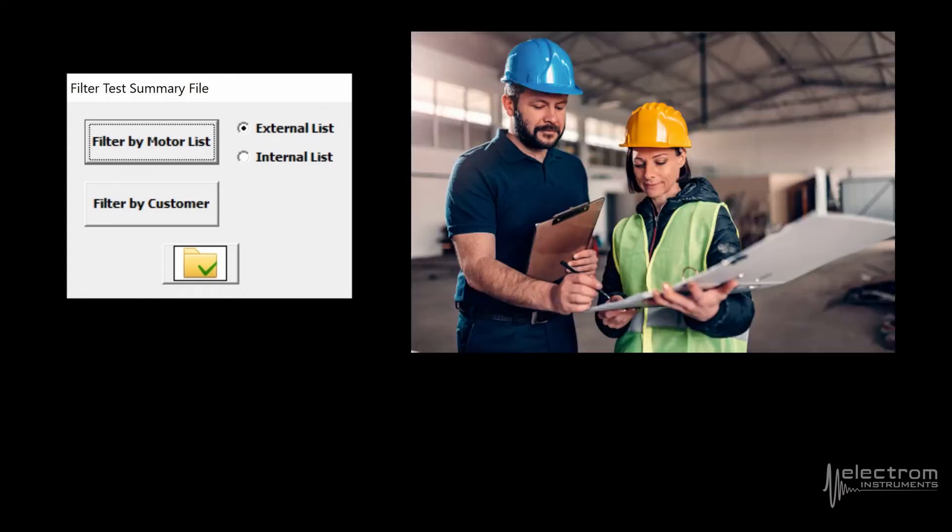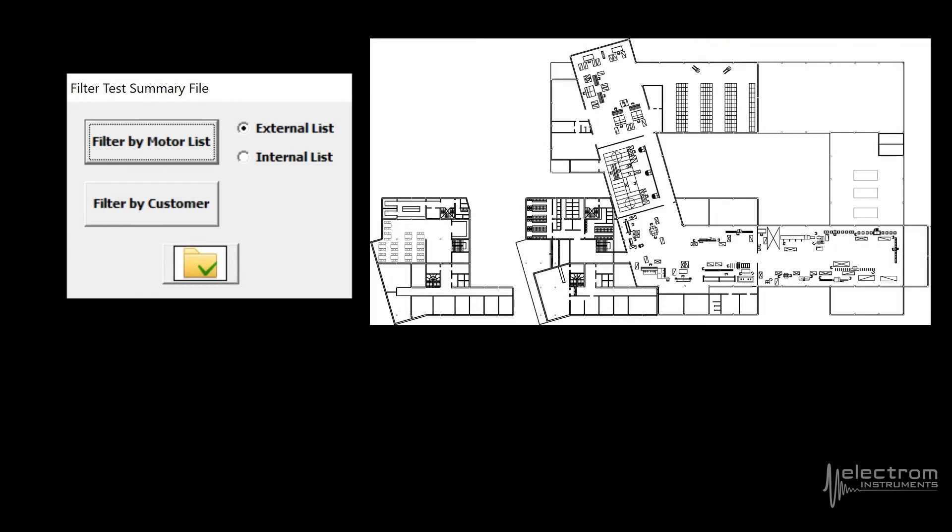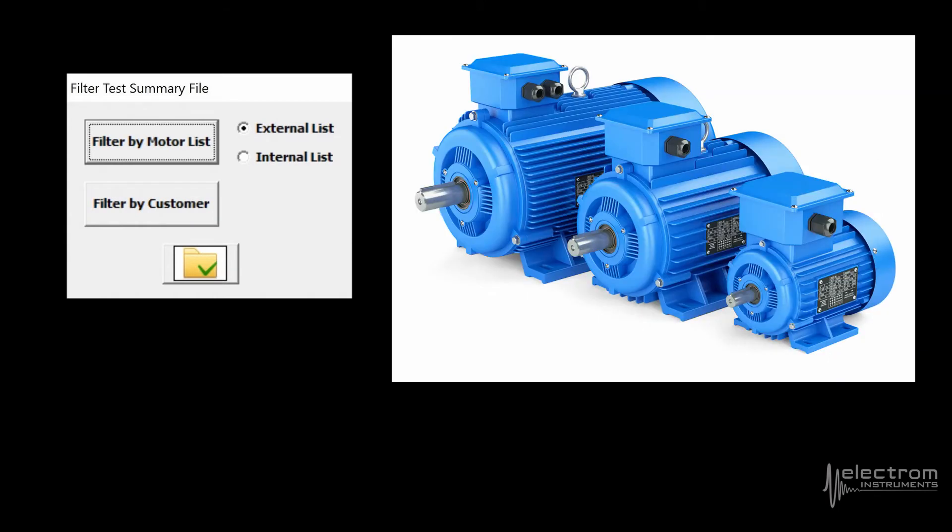Use TR Pro to filter the test summaries file to find trends and apply filters to view the data you need. For example, select test results for one customer only, or motors in pump room 1, or similar motors by voltage, power, RPM, or frame size. This way you can spot outliers in a group which may indicate a motor application problem.